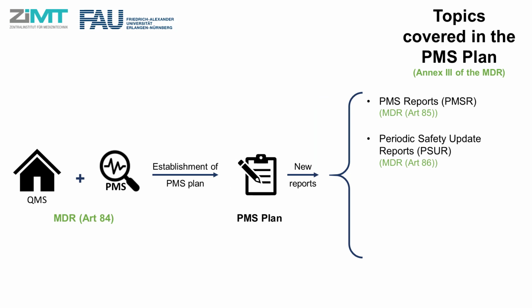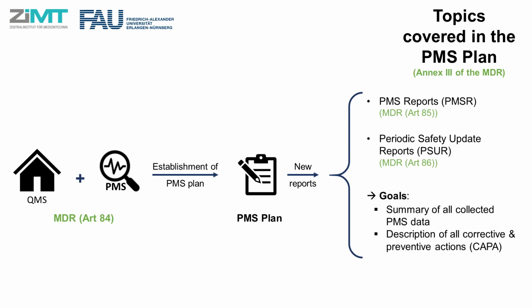As part of the vigilance reporting, the new MDR introduced two new reports: the Post-Market Surveillance Reports, PMSR, and the Periodic Safety Update Reports, PSUR. The goal of these reports is to summarize all the data collected from the post-market surveillance and describe any corrective and preventive actions, CAPA, taken during the reporting period in relation to the device.